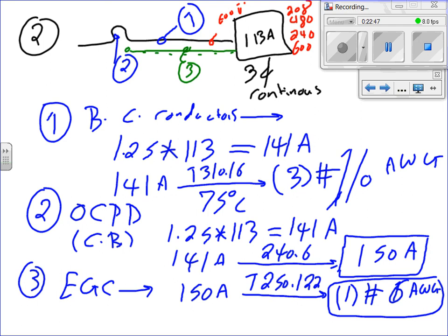Now, what's the difference? Then why? Who cares then? Why shouldn't I use any voltages? Why should I use 240 versus 208? Anybody knows? Why should I use 208 versus 240 versus 600? What decided which voltage to use? 2 things. The more power you want, the higher voltage you want to go. Always. The more power in the building you want, the higher voltage you want to go.